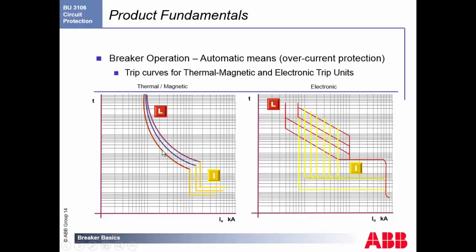However, if you know that the spike is going to be coming and you need a little bit more time to let the spike cool down or get to the motor so that the load warms up, you can pick the long curve over here, and you can see that your operation will keep on going at this spike for a longer time before the spike actually reduces itself, and then you'll keep on running for the life of the circuit. You can actually set the different levels for the L and the I based on, you know, whatever you choose.